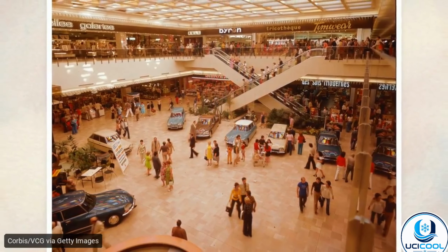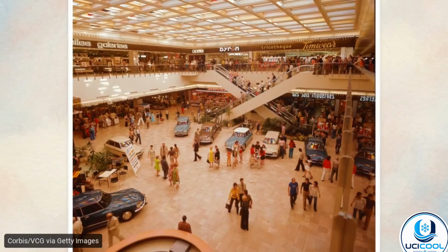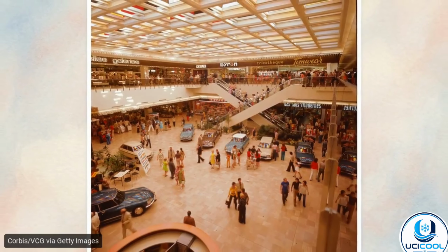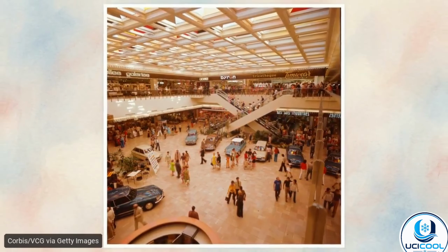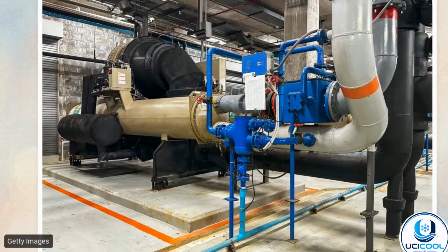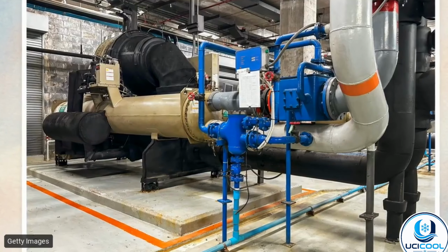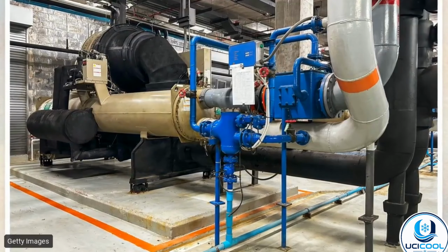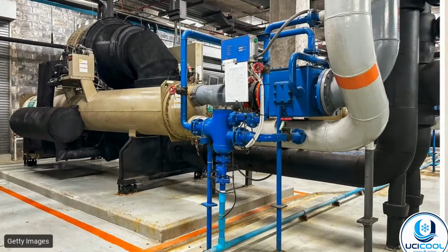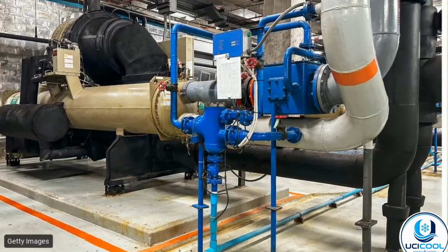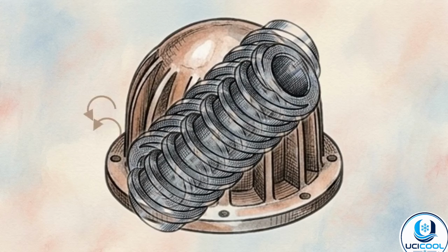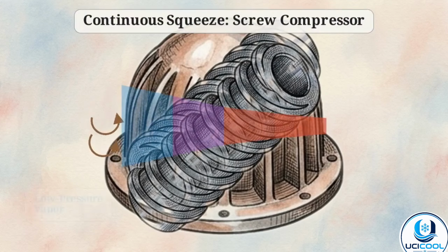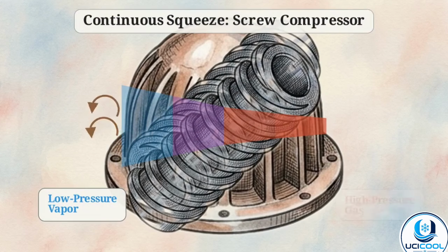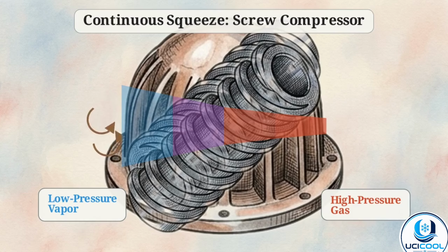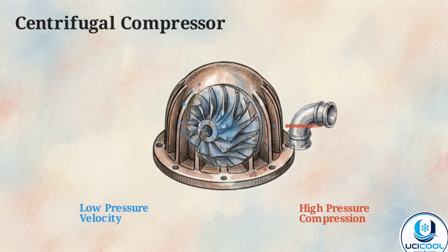At the highest end of the scale, such as in shopping malls, the volume of air to be cooled requires machines capable of high-capacity operation. Large-scale water chillers typically use screw compressors. These heavy-duty machines are built for industrial HVAC, offering long service life and continuous operation under high loads. Inside a screw compressor, two helical screws rotate against each other. As they turn, they trap refrigerant between the threads and move it along the length of the rotors, steadily increasing its pressure. The largest here is the centrifugal compressor.